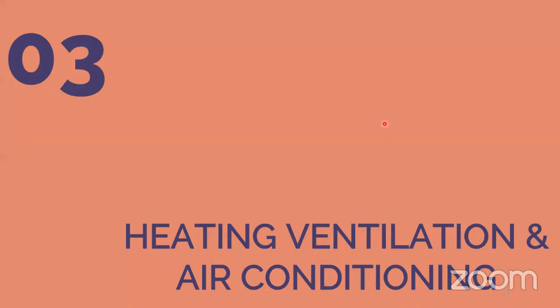Similarly, when the air is not sufficient, proper combustion will not take place. That will lead to more carbon monoxide. So both cases can be avoided by measuring the flue gas. It is an indication of whether your flue gas temperature, quantity and parameters are proper or not. That will tell you how to operate your boiler, number one. This is for our side. Number two, flue gas will have CO, CO2 and other parameters, which will create local pollution.